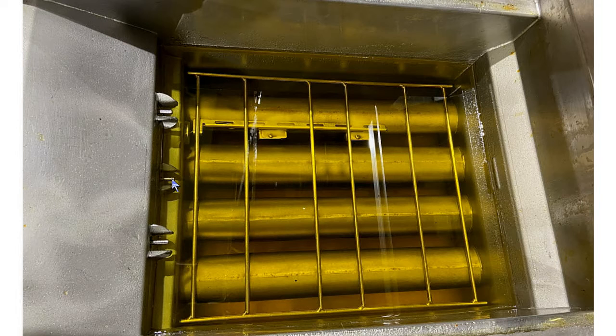So let's take a little closer look at the logic behind the E22 error code. If it's below 120 degrees Fahrenheit or 49 degrees Celsius, it's going to take a little bit longer to check, like 7 minutes, because it thinks it's cold oil, right? And if it doesn't see a rate of rise, then you get the E22 error code. If it's above 120 degrees Fahrenheit or 49 degrees Celsius, then it's only going to do it for about 5 minutes, looking for the rate of rise of temperature. If it doesn't see it, then you get the E22 error code.